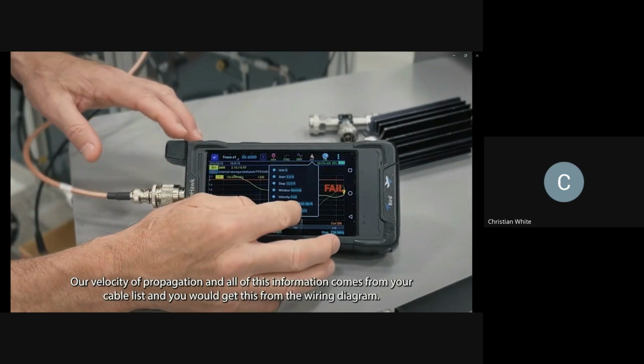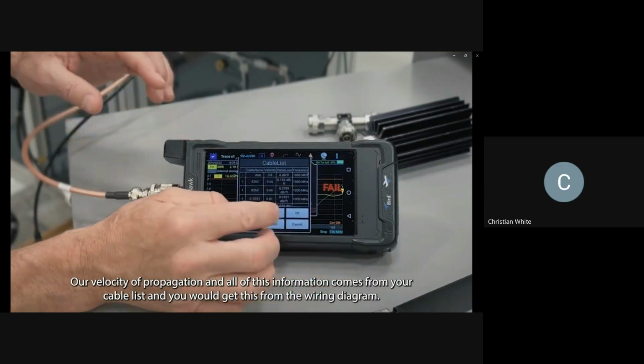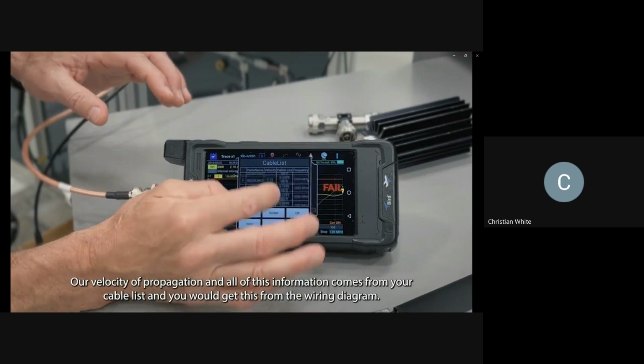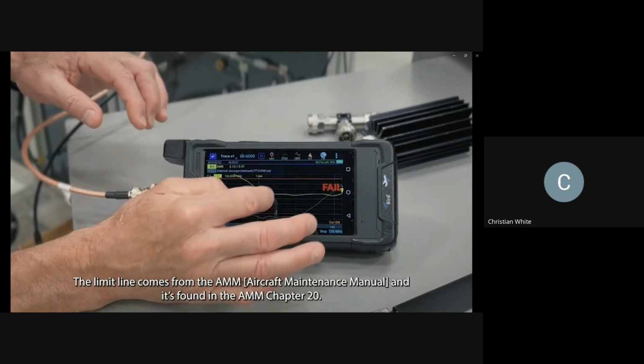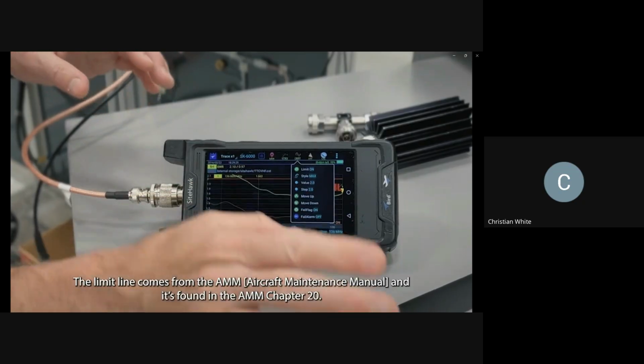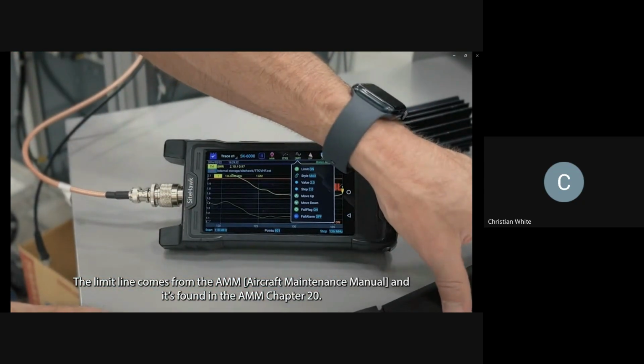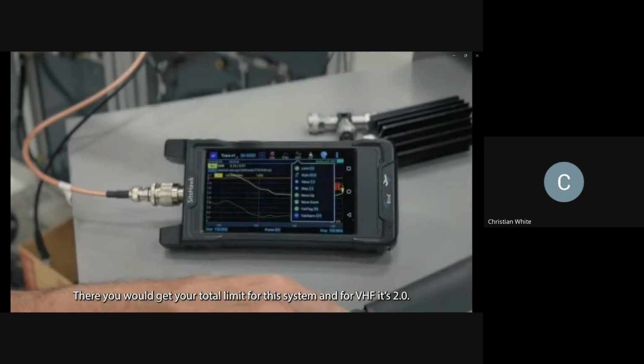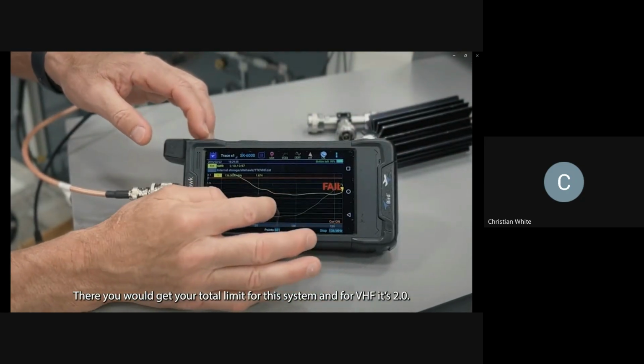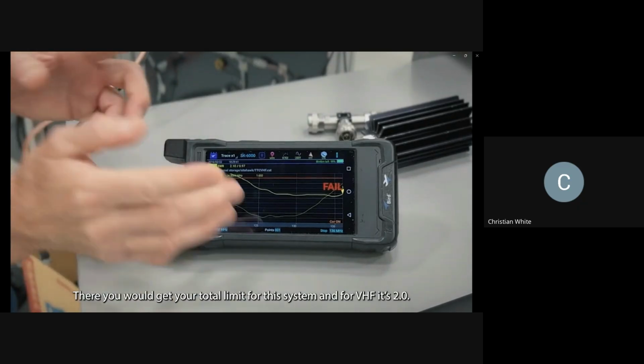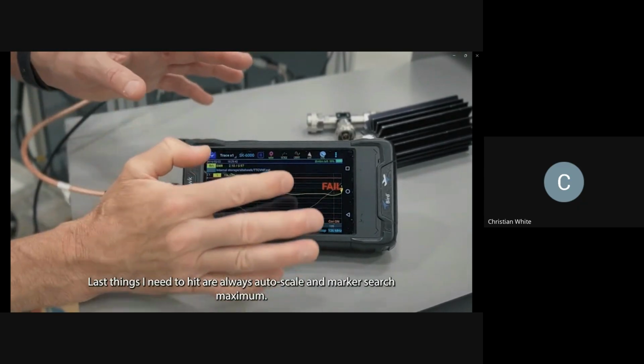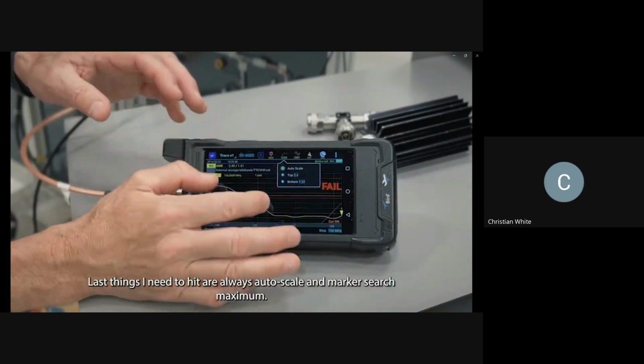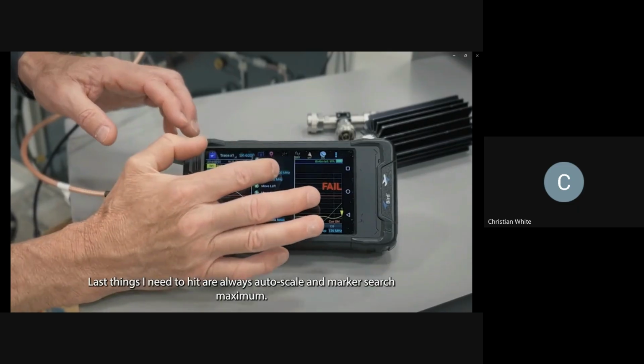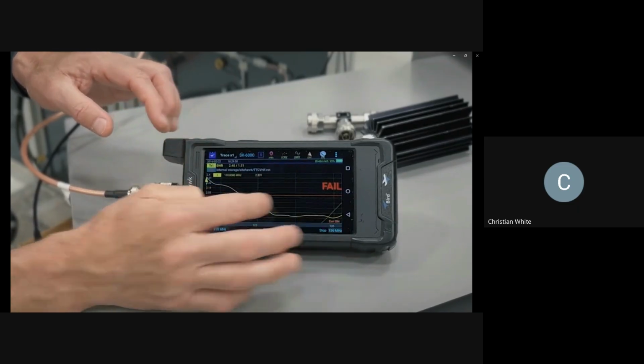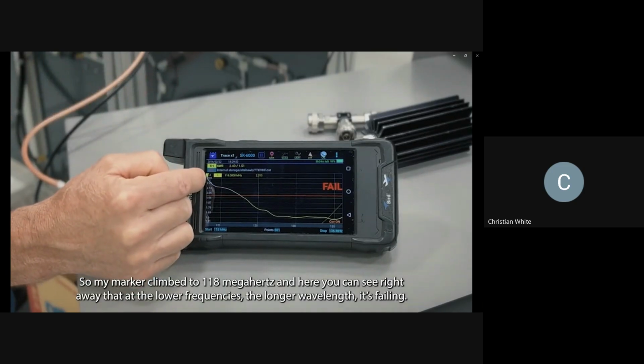Our velocity of propagation, all of this information comes from your cable list, and you would get this from the wiring diagram. The limit line comes from the AMM, and the AMM is found in AMM chapter 20. And so you would get your total limit for this system. For VHF, it's 2.0. Last things I need to hit are always auto scale and marker search maximum. So my marker climbed to 118 megahertz.